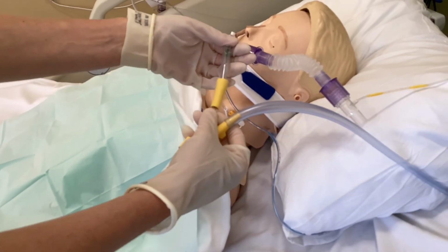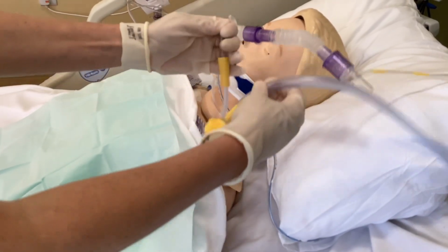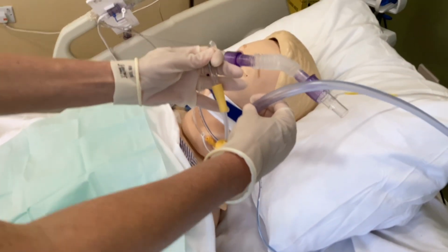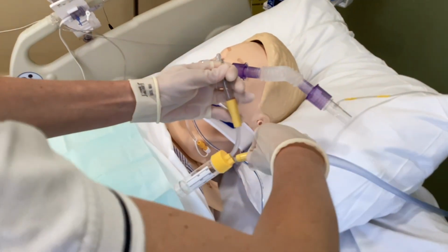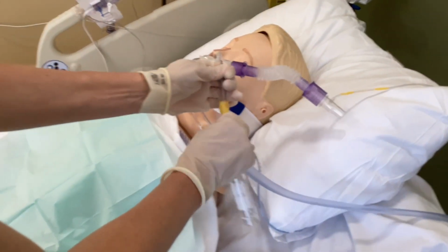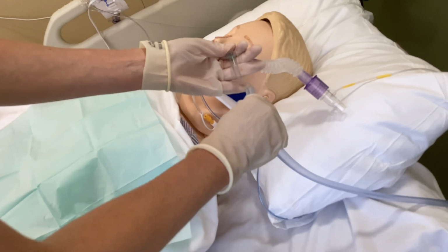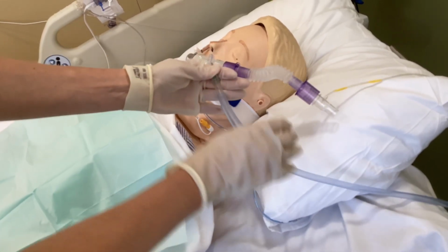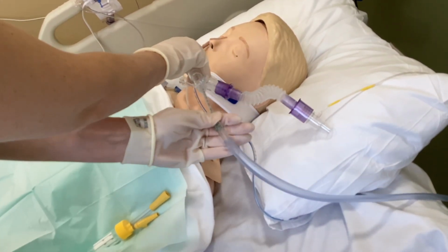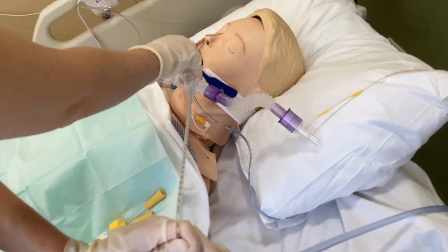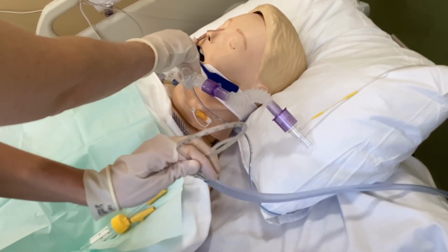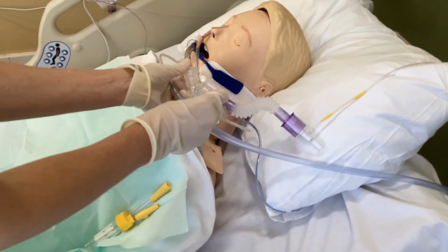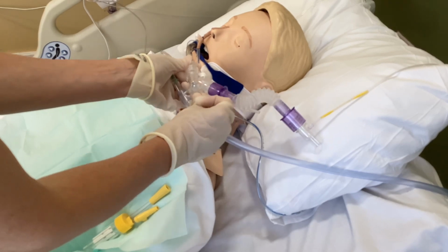Quickly remove the syringe and attach the sputum trap to the suction catheter. Keep the sputum trap upright to prevent loss of sample. If no sample is collected at this stage, the procedure is abandoned. Once the sample is obtained, remove the sputum trap from the circuit and connect the suction tubing to the suction catheter. Withdraw, applying suction throughout.